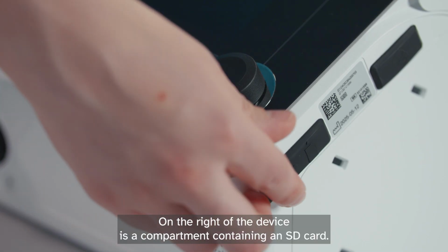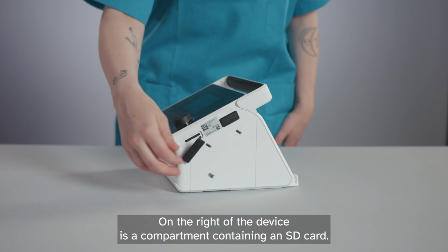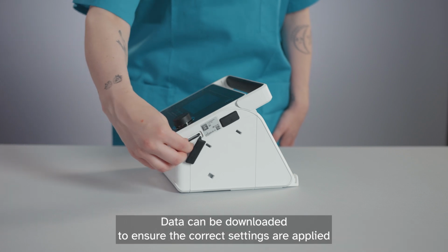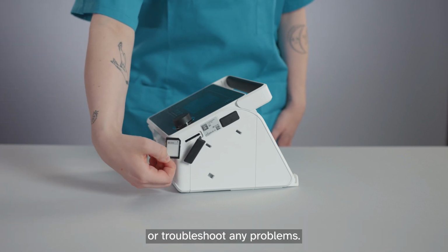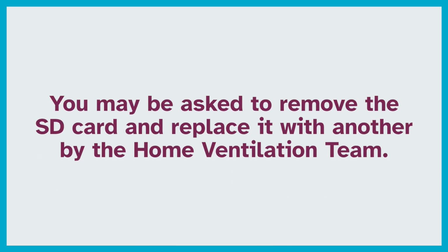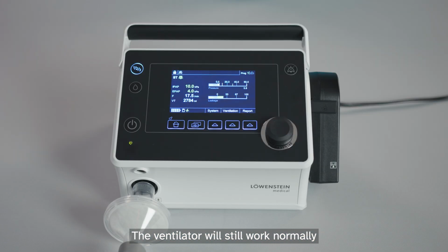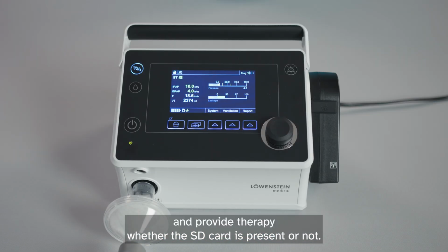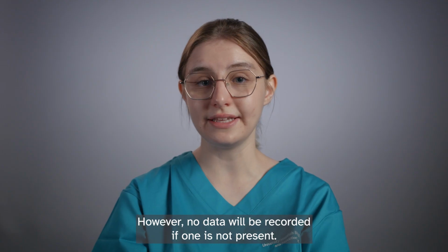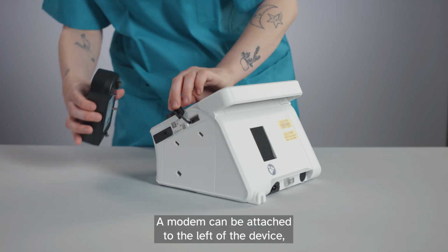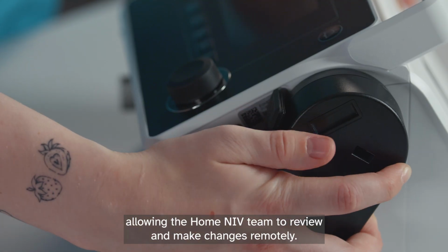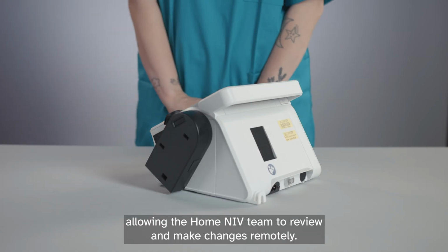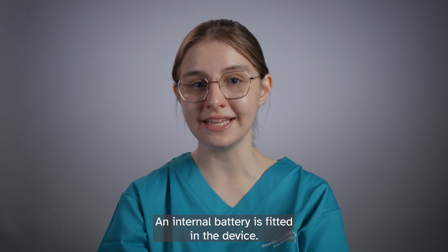On the right of the device is a compartment containing an SD card. Data can be downloaded to ensure the correct settings are applied or troubleshoot any problems. You may be asked to remove the SD card and replace it with another by the home ventilation team. The ventilator will still work normally and provide therapy whether the SD card is present or not. However, no data will be recorded if one is not present. A modem can be attached to the left of the device, allowing the home NIV team to review and make changes remotely. An internal battery is fitted in the device.